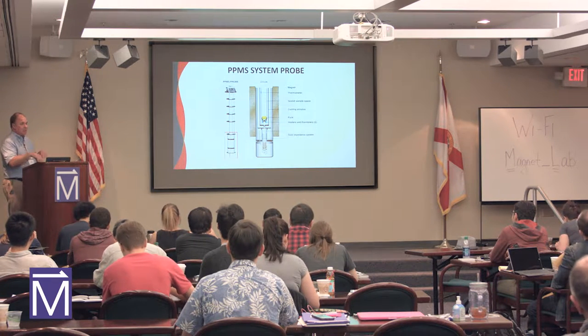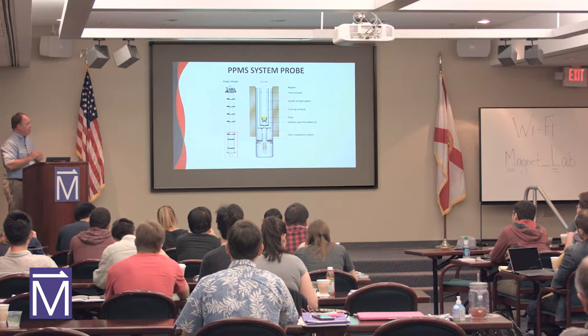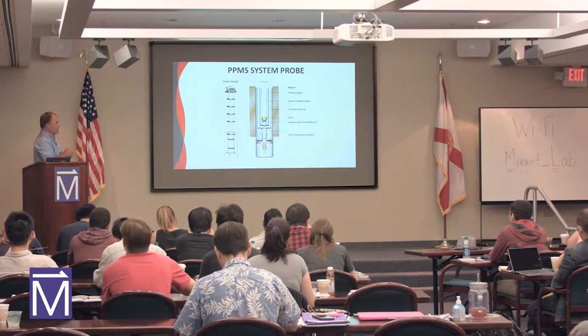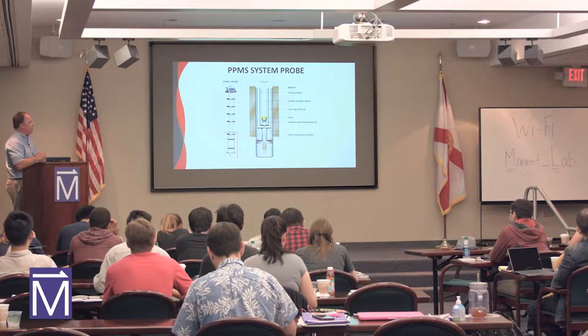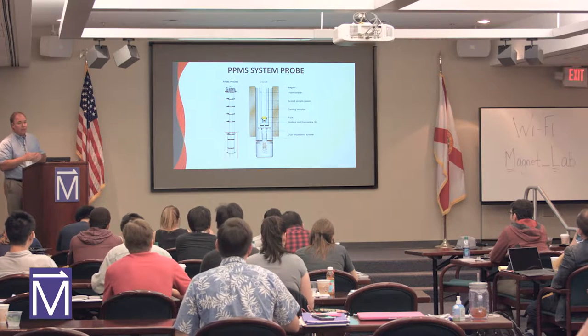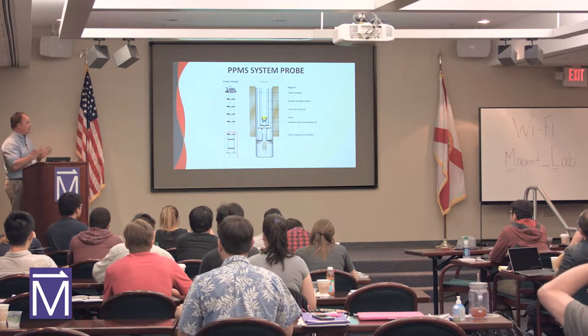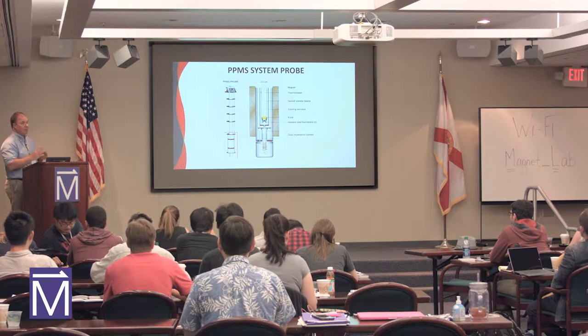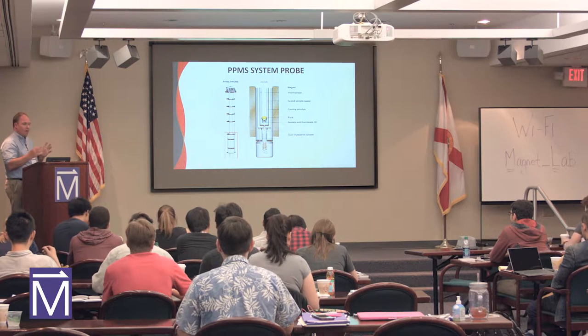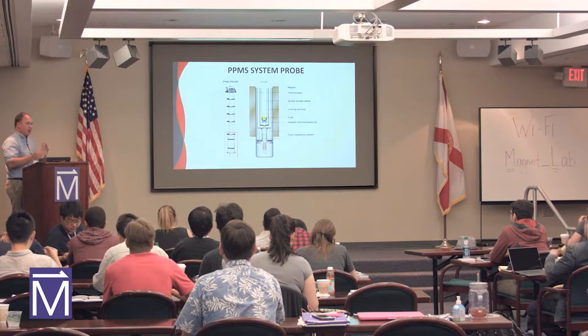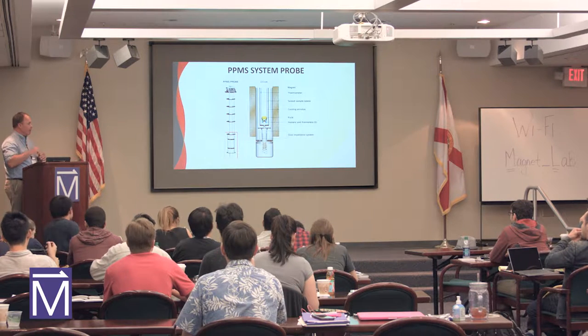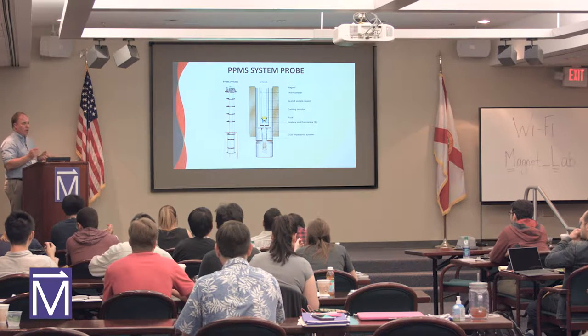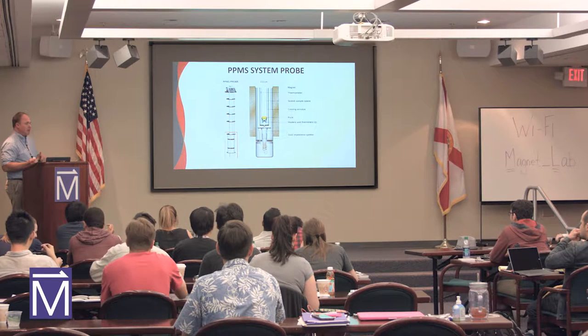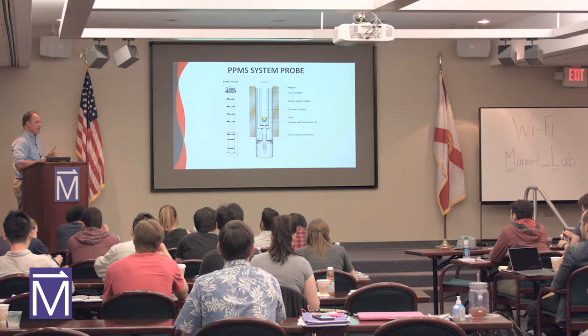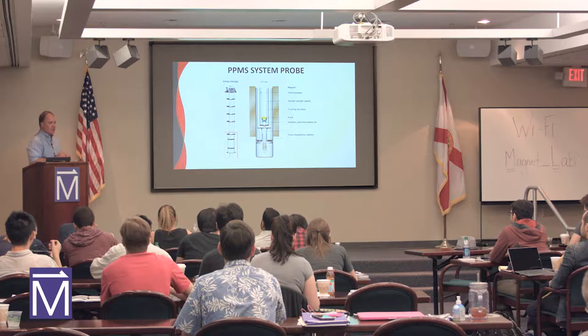In the wet system, there are some pickups to pick up the liquid helium. We've got a control system with a couple of impedance flows so that we can control the impedance and flow of the helium through the sample space. So the magnet's cold, but then we have a separate cooling circuit that we can pick the liquid helium up into to cool the sample. And we've got high temperature flow plumbing and low temperature flow plumbing, so we can get good temperature control and stability.